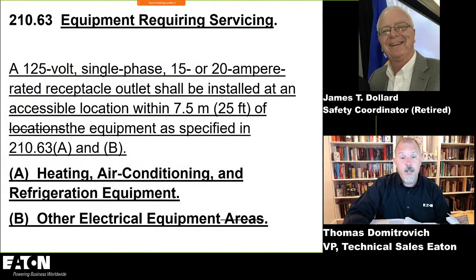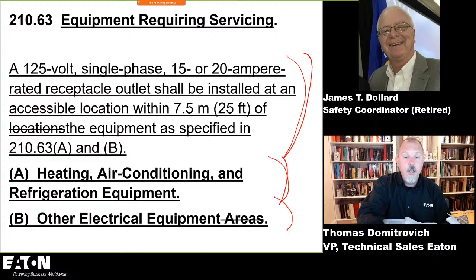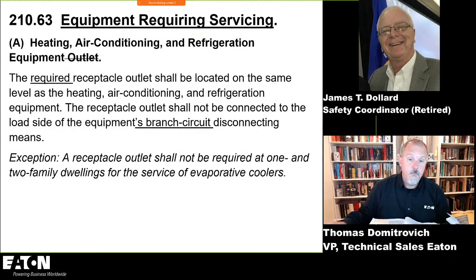And then we changed the equipment requiring servicing. We reorganized it. We have the parent text here that gives you your overview, and then we have your A and B, which covers heating and air conditioning, your HVAC equipment, and then other equipment areas. This one here just talks about your outlet for HVAC. Required receptacle shall be located where it needs to be located. I don't think we changed the intent of this, but we just added some rewording. The whole gist there is you want to make sure that receptacle is there for use when they power down the equipment for their testing and lights and whatever else that they might have, right?